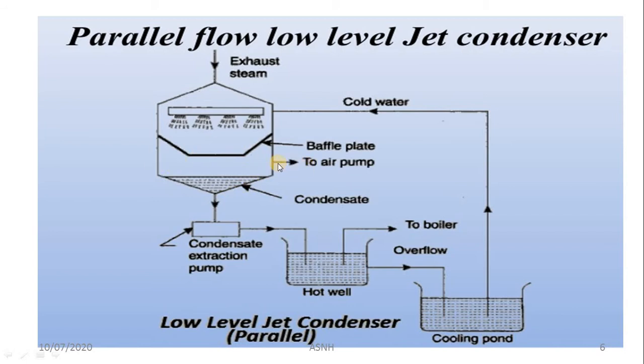Also there is one most important element, that is the air extraction pump. The name of that pump is the Edwards air pump. The main function of the Edwards air pump is to remove the air which is available in the condenser shell to maintain the proper vacuum inside the shell. It is mandatory to remove the air available in the condenser shell, so that is why the Edwards air pump is used. There is another pump, the condensate extraction pump. The main function of that pump is to move the condensate, which is just water, into the hot well. So these are the basic important components of the parallel flow condenser.